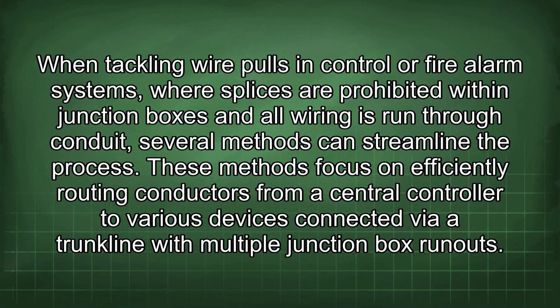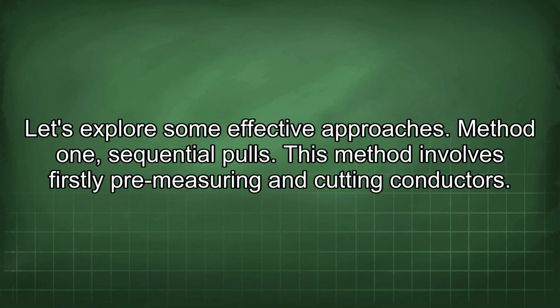When tackling wire pulls in control or fire alarm systems where splices are prohibited within junction boxes and all wiring is run through conduit, several methods can streamline the process. These methods focus on efficiently routing conductors from a central controller to various devices connected via a trunk line with multiple junction box runouts. Let's explore some effective approaches.